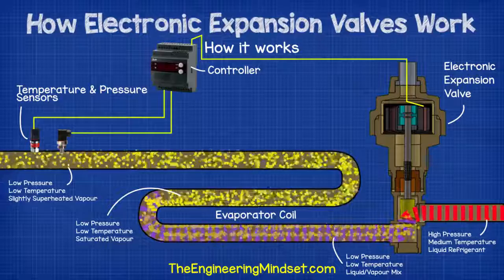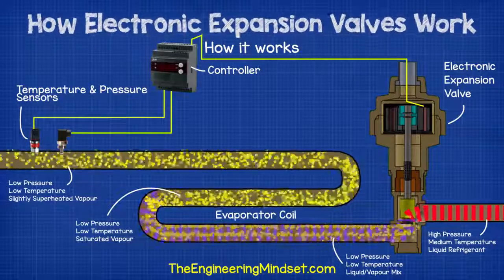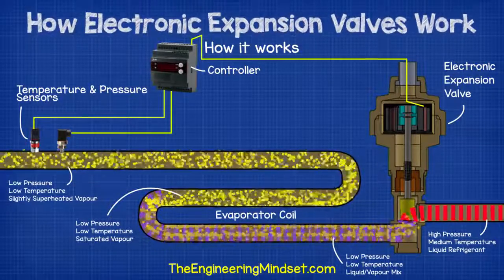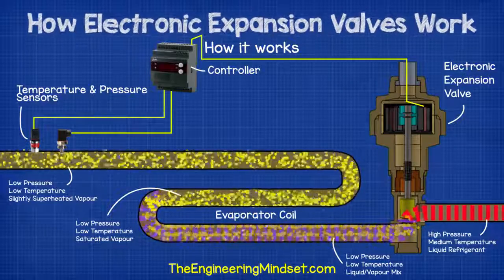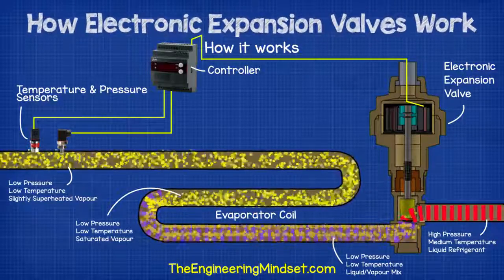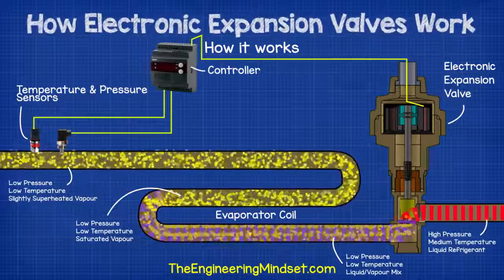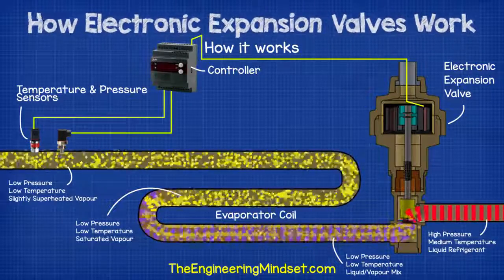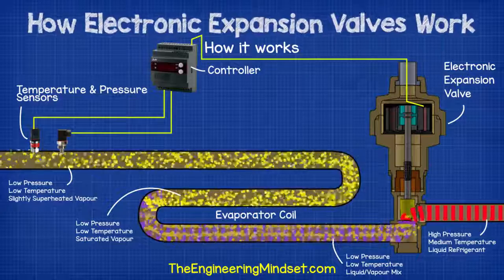Some simple ones will use a single thermistor at the evaporator outlet. Some will use two thermistors, one at the inlet and another one at the outlet, and then use a temperature differential as the superheat. But we're going to focus on the pressure and temperature method in this example as it's a very reliable method and one you'll likely come across in the real world.